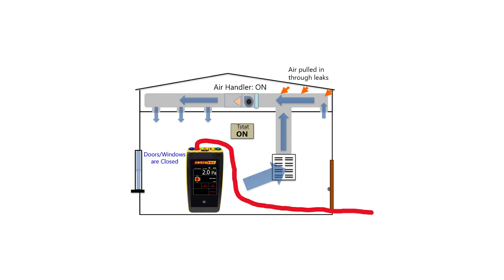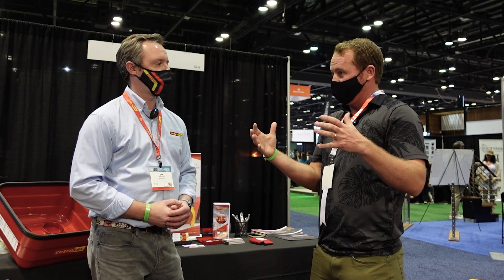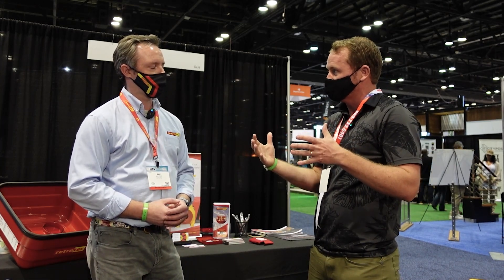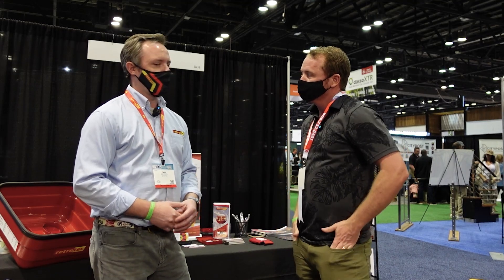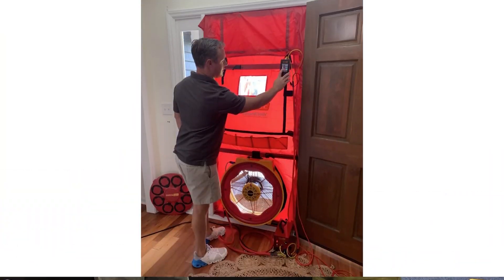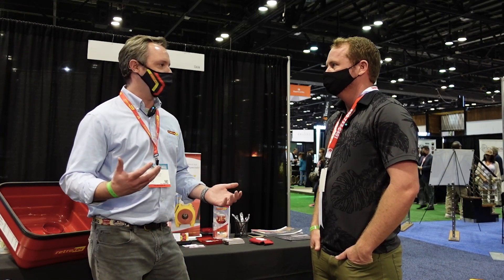What we don't think about sometimes is if you have a room that's getting too much air put into it and not enough into another — meaning there are imbalanced pressures — that also results in a very similar dynamic. And it's such an easy thing to check. If you already have a blower door, a duct tester system, or a high-precision manometer, just shut the door, toss the tube underneath, let the system run, and see what that pressure difference is.